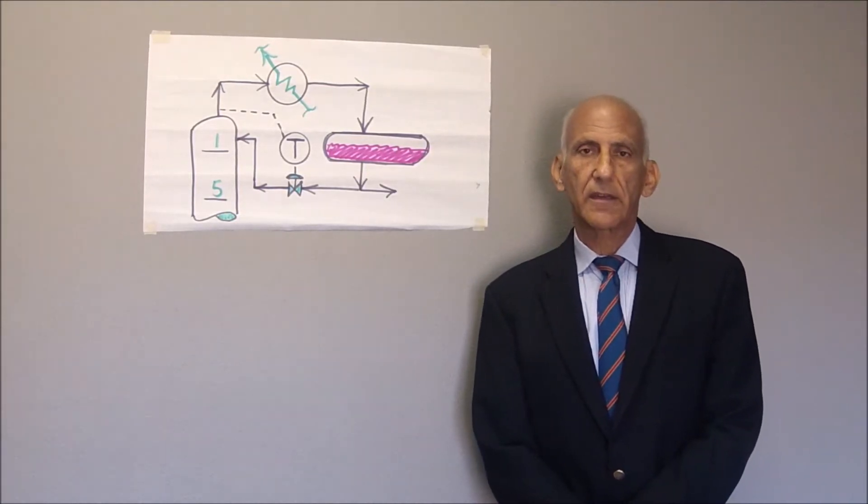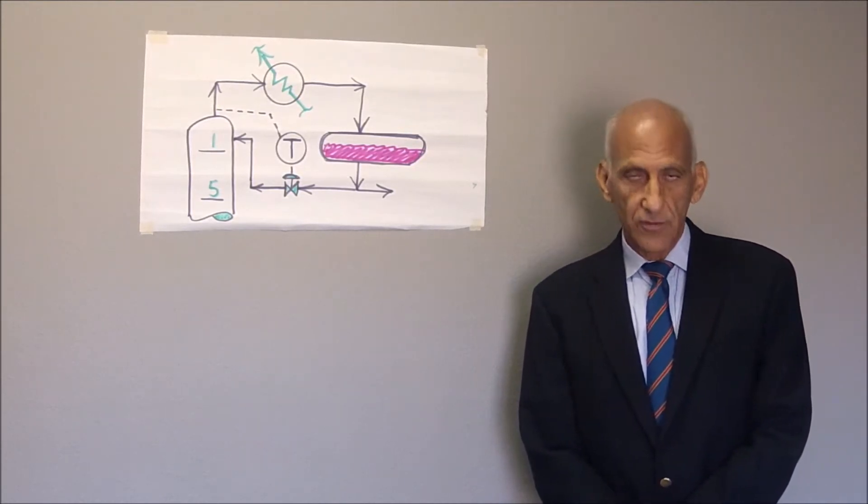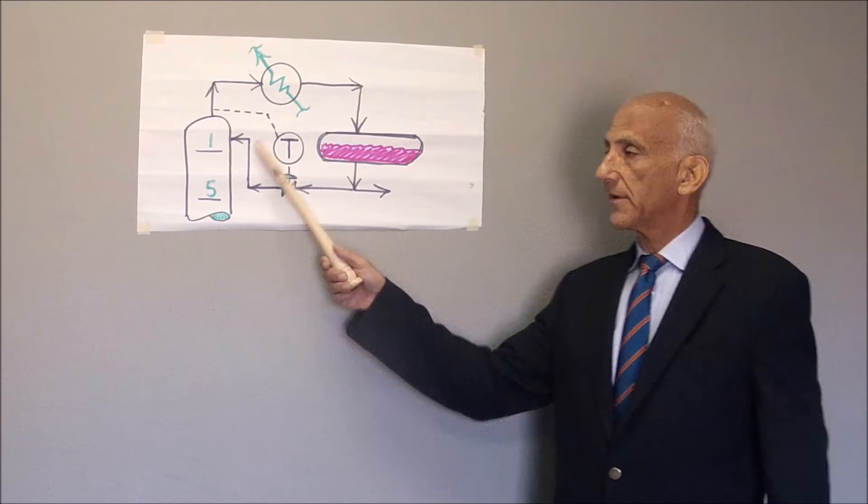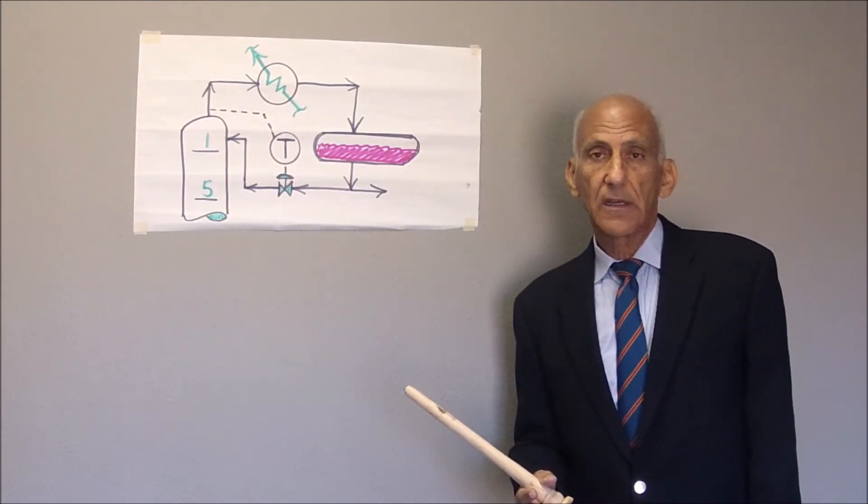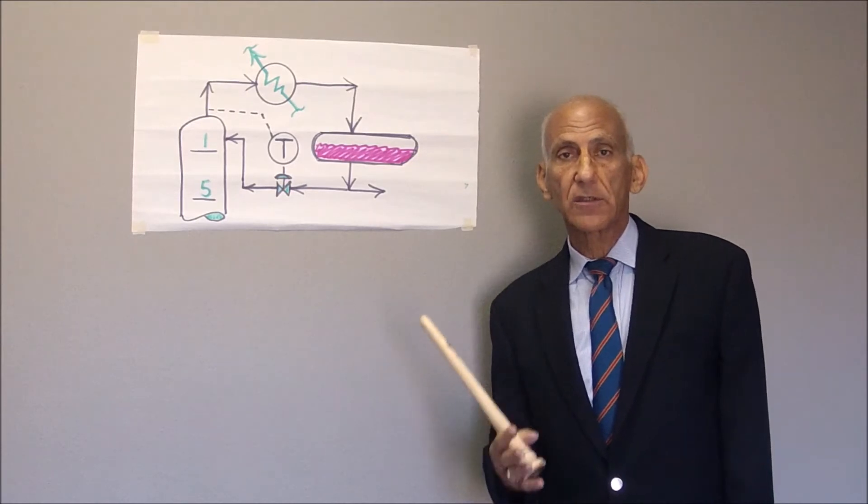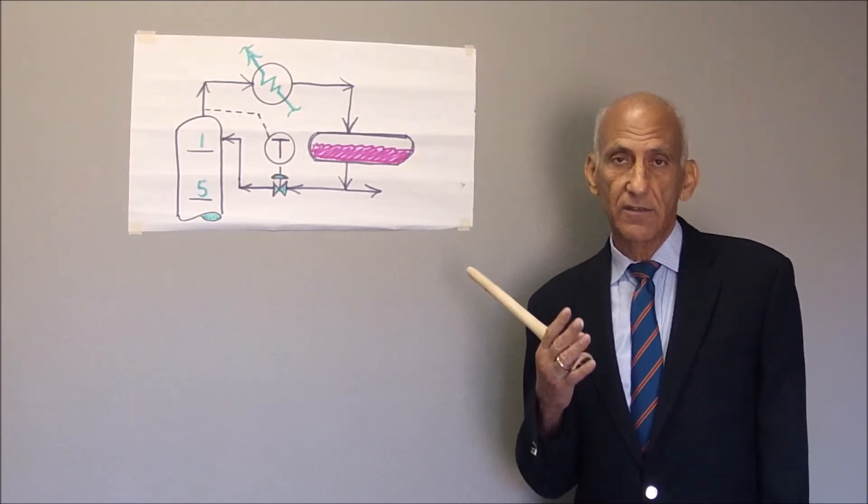Unfortunately, while it is our intent to reduce tower top temperature by adding more reflux to cool down the top of the tower, at some point you will cause the top tray to start to flood.